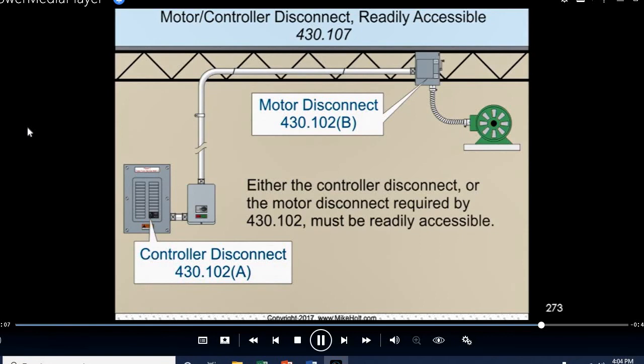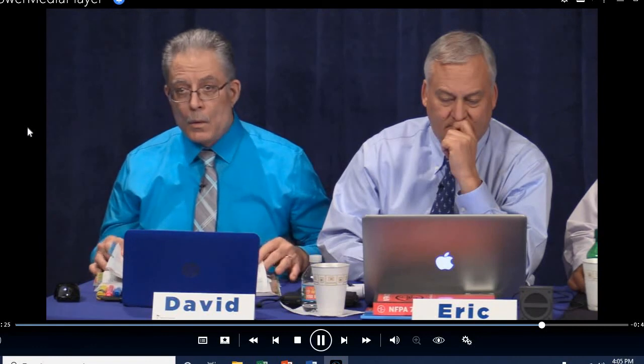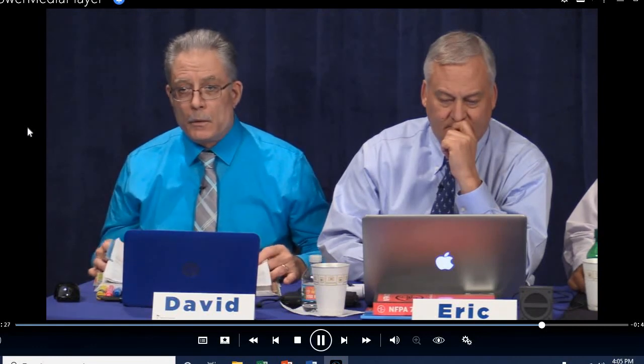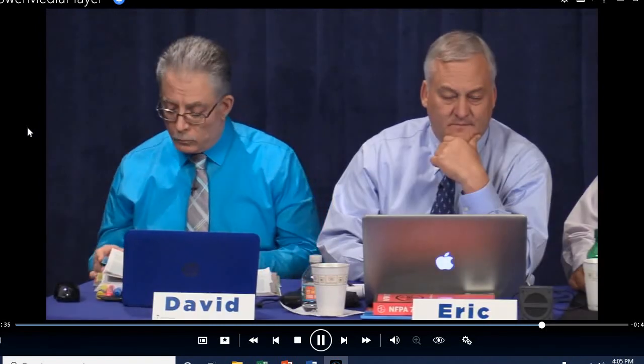Now, I guess this is where we have to kind of lean on that switch rule, don't we? Yeah. Not located more than, but you know what I'd like to see, Dave? If we're looking for the switch rule to apply to 6 foot 7 inches, unless it's adjacent to the equipment and readily accessible, I'd like that information to be placed in 430. Not that I have to know that, okay, well, this is a switch also, so now we got to go to 404. Even for air handlers. I'm sorry? Even for air handlers. Yeah, in other words, I think the requirements on the height of switches and readily accessibility should be in the articles where disconnecting means are required, so they don't have to go to some general rule.